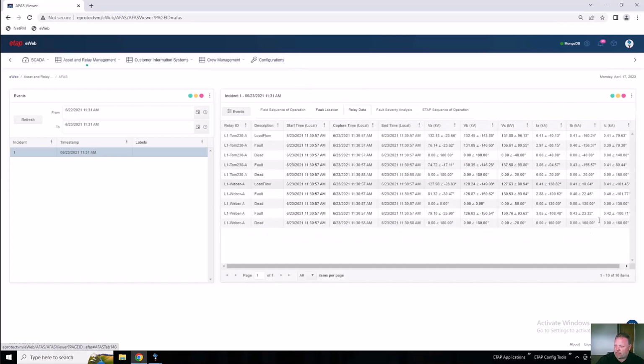Next, we have the relay data. Here, again, let me expand this out and show everything. Okay, so here we can see each COMTRADE file that we received. We received a disturbance record from relay L1 TOM230-A, and then we received a disturbance record for L1-Weber-A. What's important here is we take that COMTRADE file, or that waveform, and we analyze it and separate that waveform out into various zones. For instance, load flow is the initial condition, and you can see for both L1 TOM230-A and L1 Weber-A, the initial state is that load flow. So it's the initial conditions.